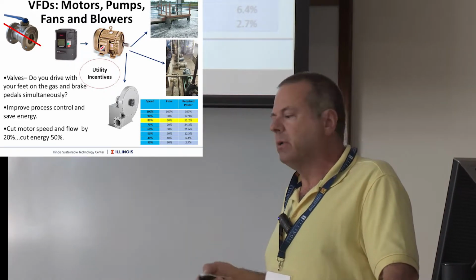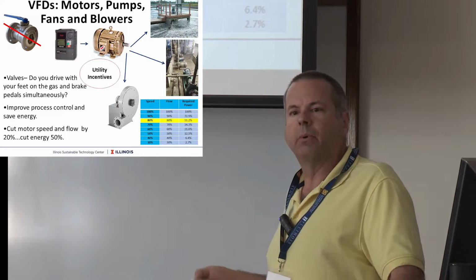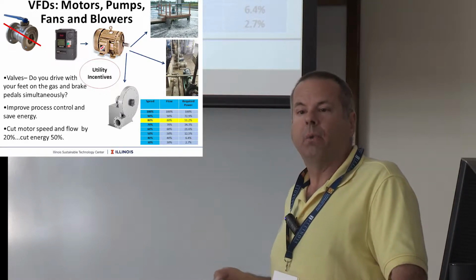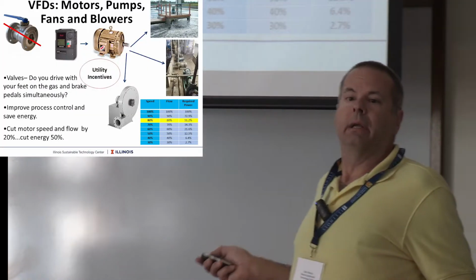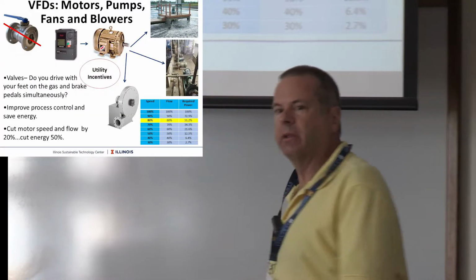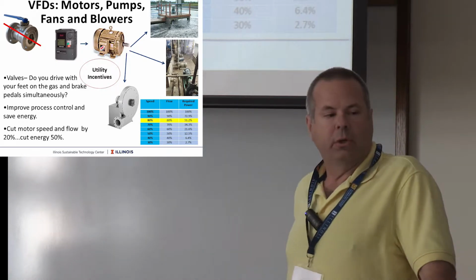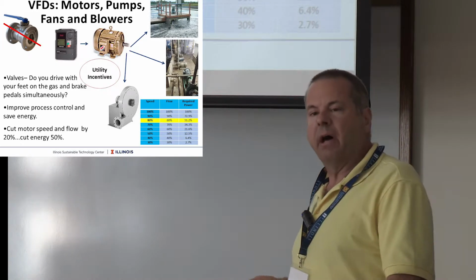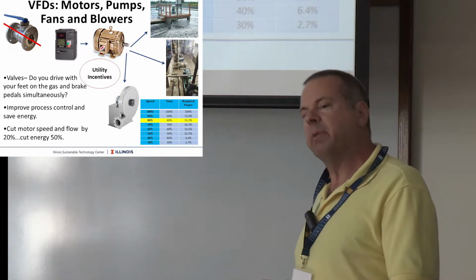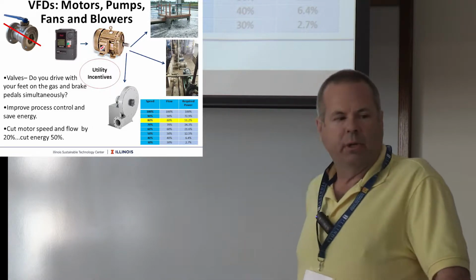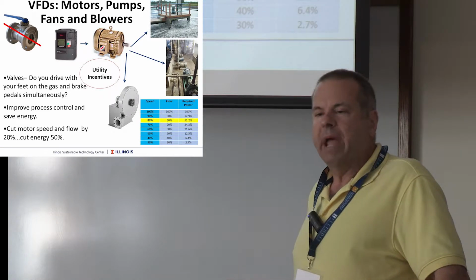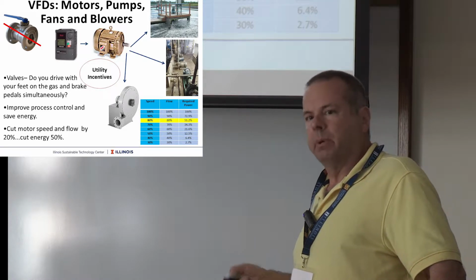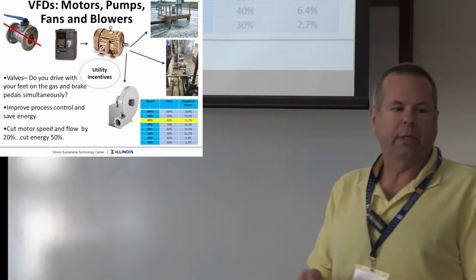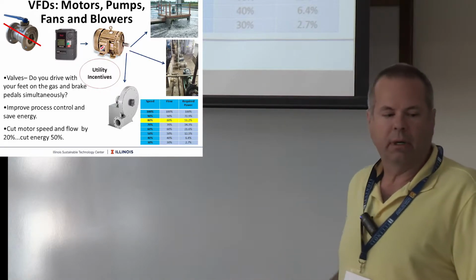It's not unusual for us to walk into a facility and see a pump or a blower running wide open, but downstream of it, there's usually some kind of throttling mechanism, a valve or damper. That's money, money, money, every day of the week. So that's low-hanging fruit. If you were to open up that valve, let's say it was closed just 20%. If you open up that valve 100% and you put a variable frequency drive in there, slowing that motor down, matching the speed of the motor and of the pump or blower to the load that is usually ever changing, that's why you've got the valves on there.